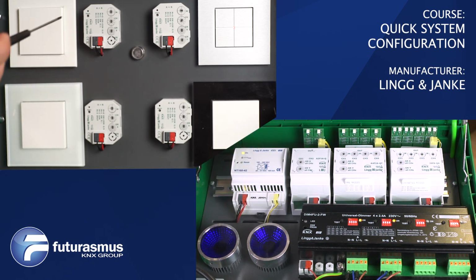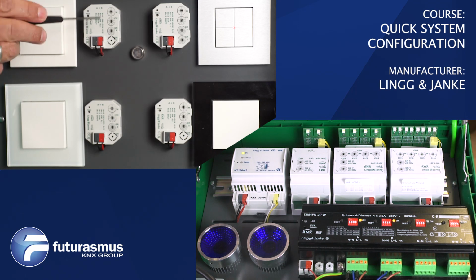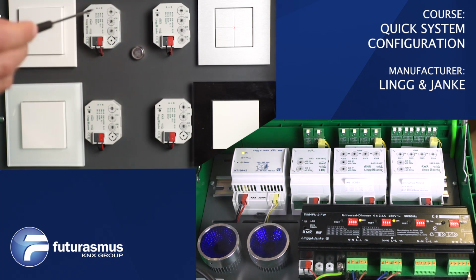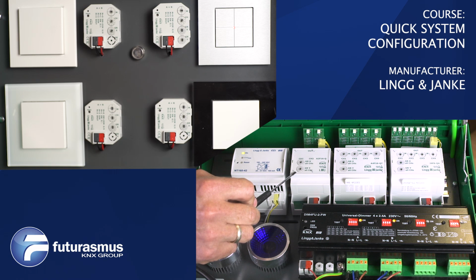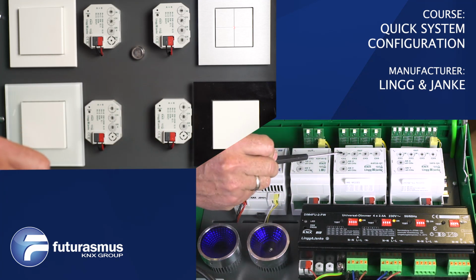So now let's have a look at how it works. Let's set this one, for instance, to a very easy function: function 1, which is switching on and off. Then we set this one here to channel 1, and we use the group, let's say group 2, to put all of them the same. So the switching function, channel 1, and group 2. Then we go to the on-off switching actuator. There we set the channel to channel 1, and the group here we set to 2. So we've got channel 1, group 2.